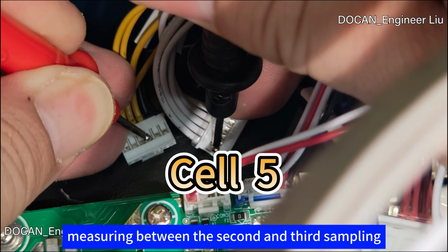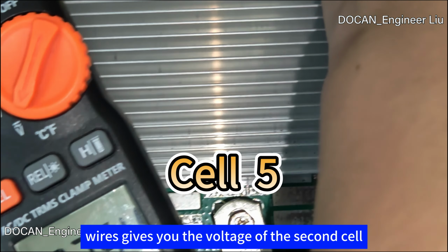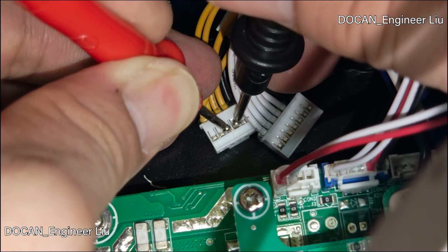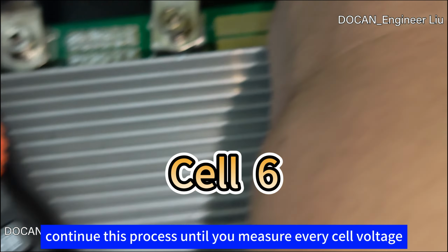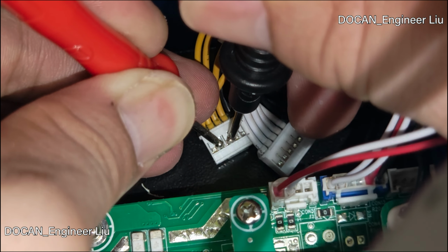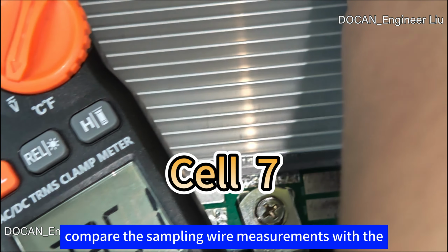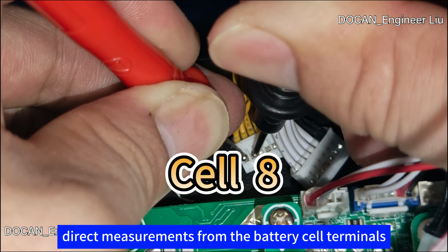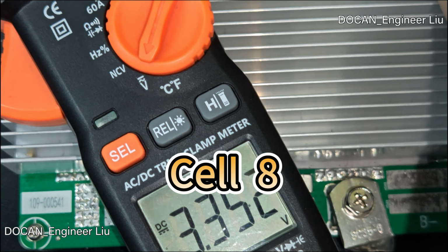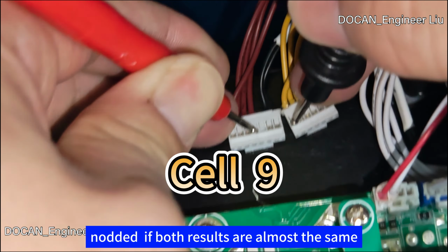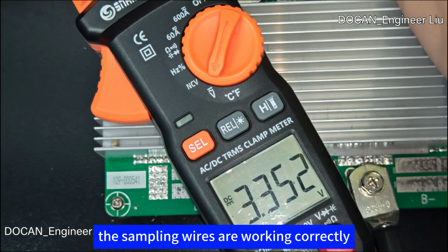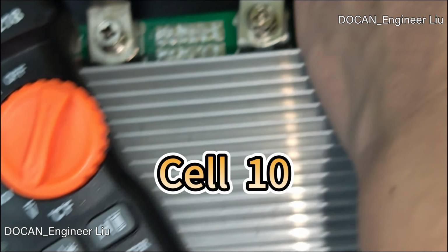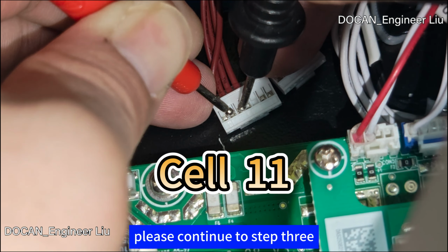So, measuring between the first and second sampling wires gives you the voltage of the first cell. Then, measuring between the second and third sampling wires gives you the voltage of the second cell. Continue this process until you measure every cell voltage. After that, compare the sampling wire measurements with the direct measurements from the battery cell terminals. If both results are almost the same, the sampling wires are working correctly. Please continue to step 3.